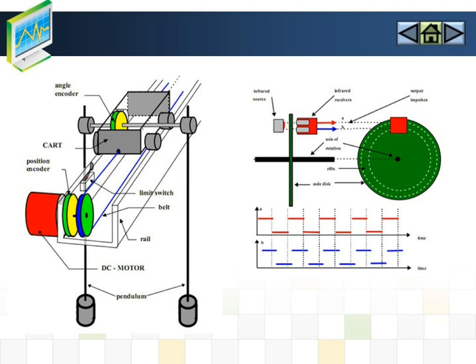The light beams, emitted by two light sources A and B, go through two rings of slits on the disk. The slits have a phase difference so that the electric output receivers A and B are rectangular waves with a phase difference. The sign of the phase difference allows the direction of rotation to be determined.